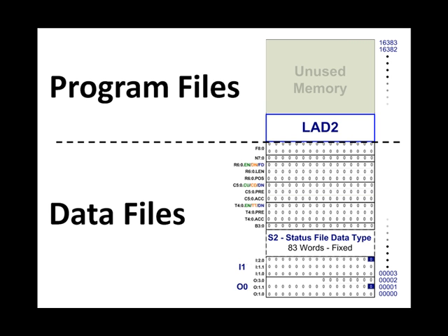But the program files, the ladder logic itself, in some of the processors in this family, you can edit and change those online. The smaller processors in this family of products, with the exception of the newest one, do not allow online editing. The larger modular processors do allow online editing, but none of these processors allow you to shift the size or shape of the data table files, much less create a new data table file while online with a processor.